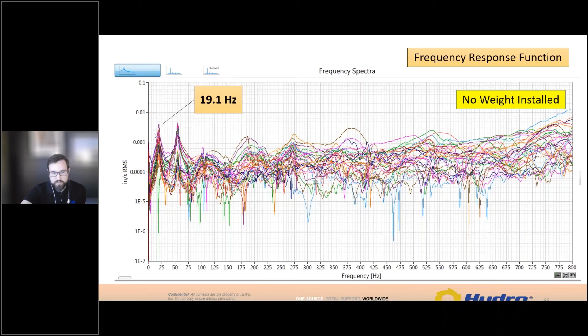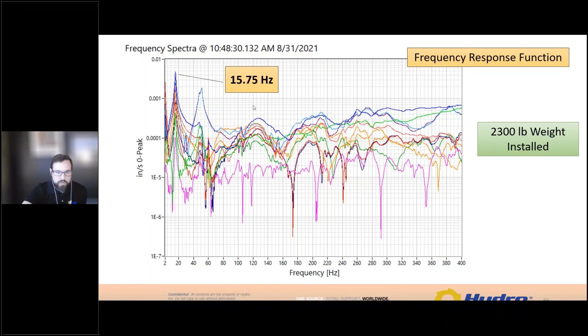So again, with no weight installed, we've got this 19.1 hertz peak. And then with mass installed, we've shifted that peak down to 15.75 hertz. So that's the kind of effect that we're going for. And as a result of that, just by adding the mass, we end up dropping this peak at 1 times down by 66%. So this reduction in amplitude allowed this machine to be within the limits.